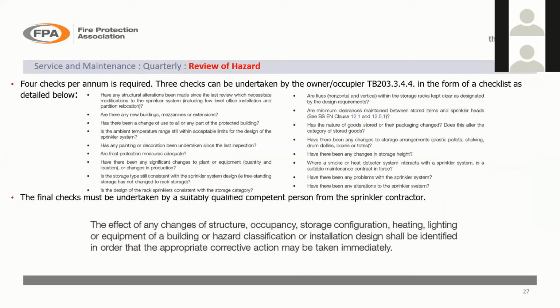I did mention earlier on review of hazard. This is very important. It is one of the things that often doesn't get carried out. It's one of the things that we've seen during our independent third-party inspections that we carry out. There need to be 4 per year. That's 1 every quarter, 3 of which, depending on the kind of business that you've got, could be undertaken by the owner or occupier in the form of a checklist. But the final check must be undertaken by a suitably qualified, competent person from the sprinkler contractor.